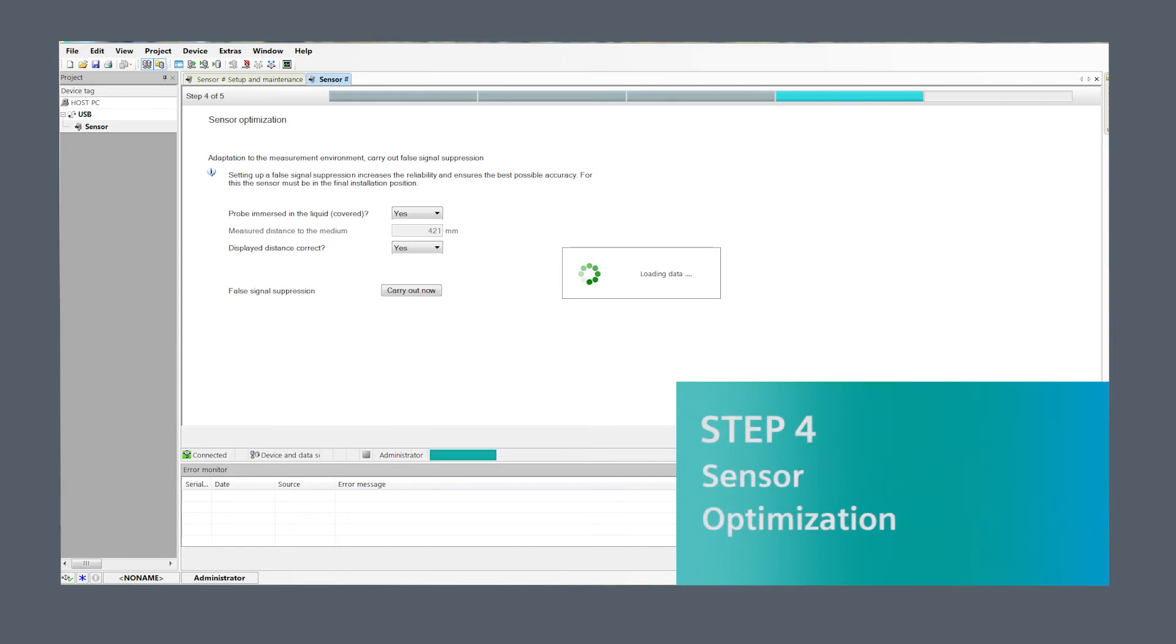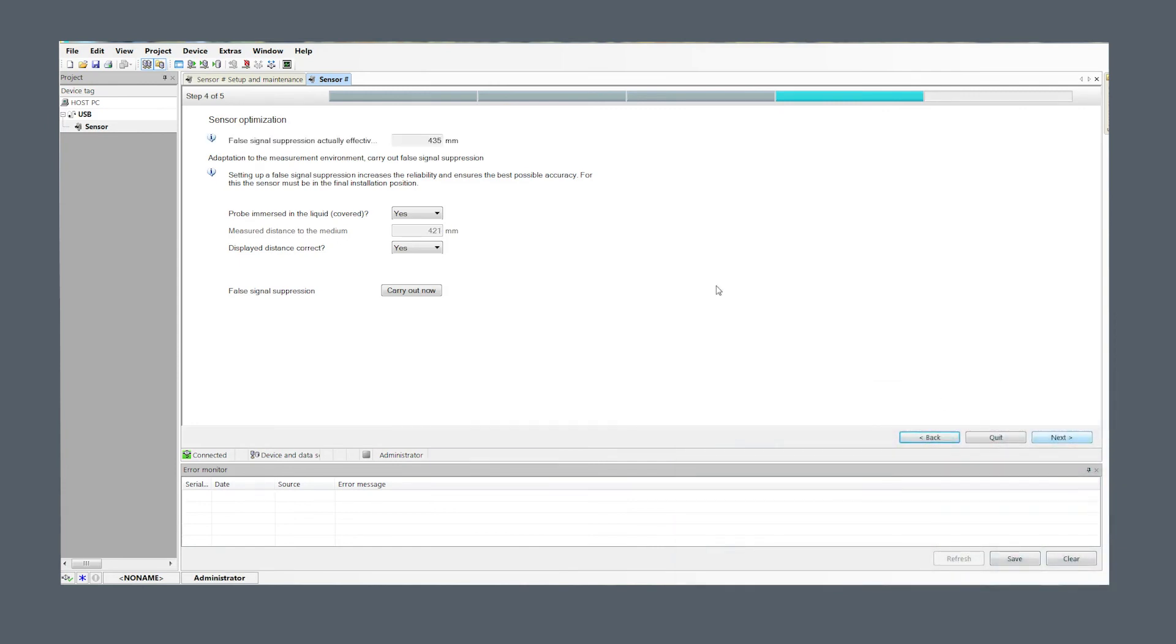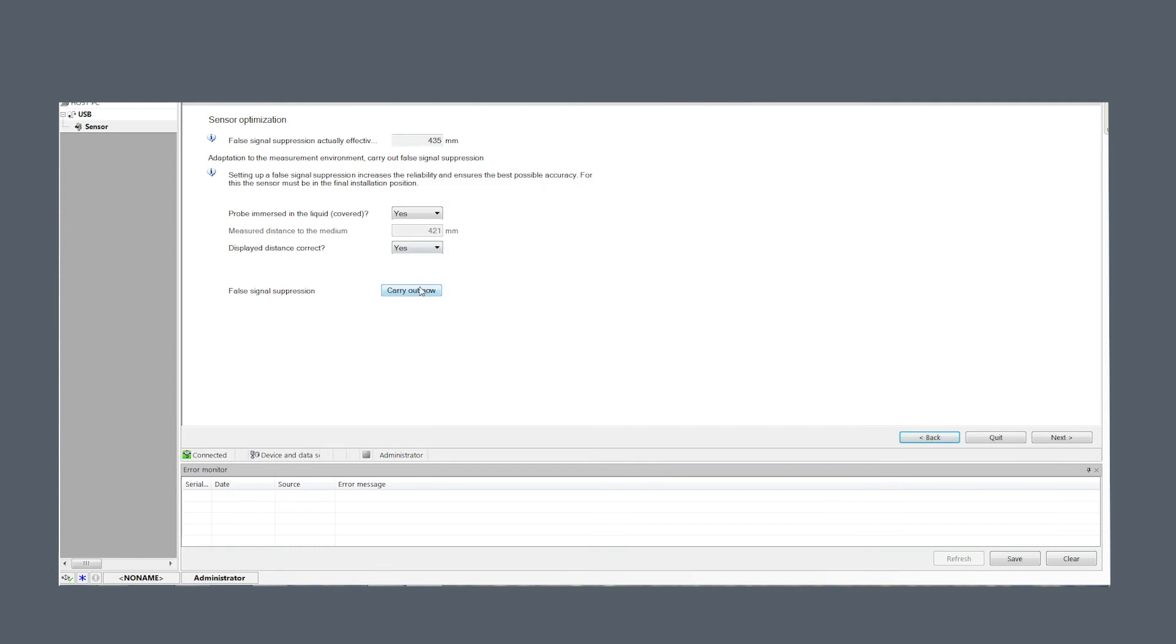Step four, sensor optimization. Current sensor false signal suppression effective distance is shown. A new suppression can be carried out if the sensor is in its final installation position and if covered, reported distance to material is correct. If distance is not correct, the correct value can be entered.